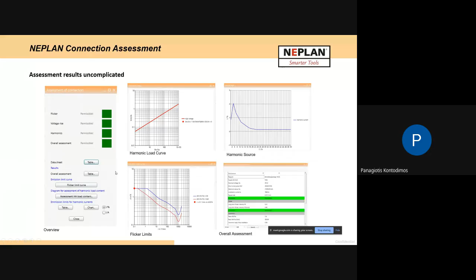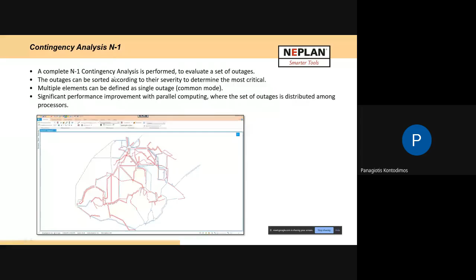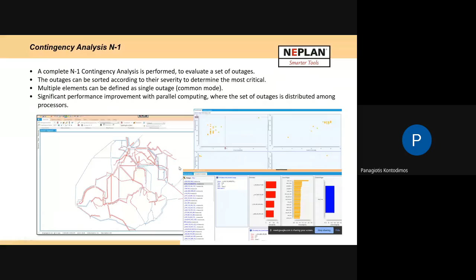For transmission, we have different modules. Especially interesting is the contingency analysis N-1, where we specify the outages, then we make a ranking of the outages, and we can see if we lose, for example, this line, whether there's a violation in the system. So my network is not N-1 secure, and I can study ways to make the network secure under different scenarios.